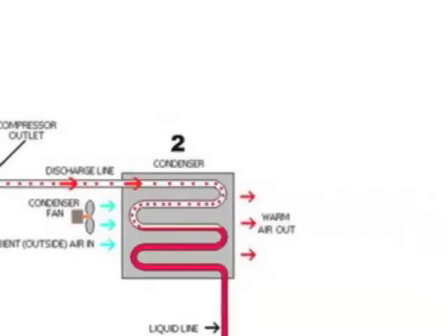At our condenser coil, we have a fan that's blowing outside air across the condenser coil that the refrigerant is traveling through. And even though it may be a 95 to 100 degree day, that air is still cooler than the temperature of what's inside of our condenser coil. Going to get it below that saturation point. So as our refrigerant moves through the condenser coil, it begins to cool down and the heat's released out into the air. And we make it to our saturation point and become a liquid, and then we eventually become cooled below that point where we have subcooled refrigerant.